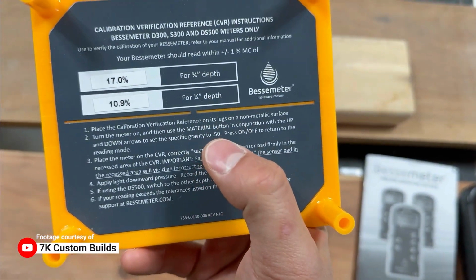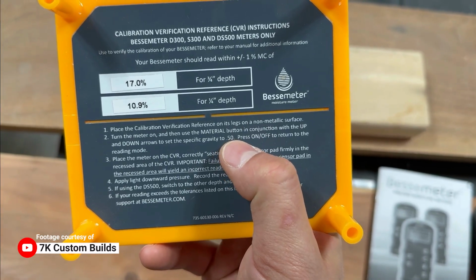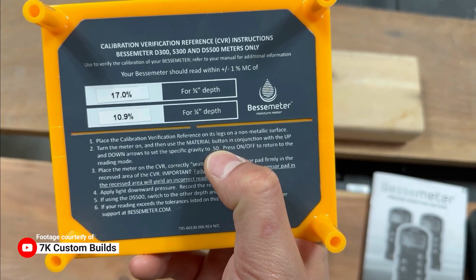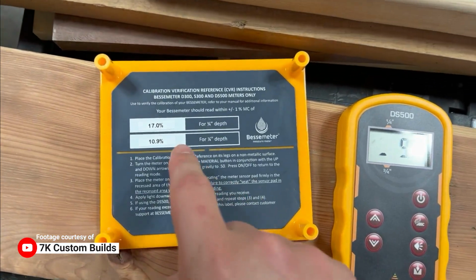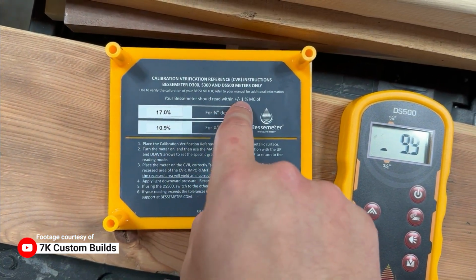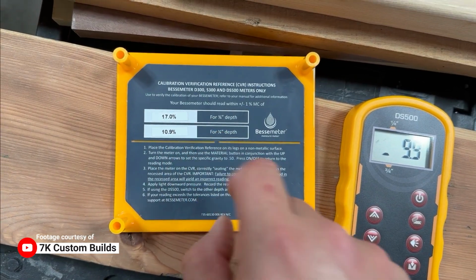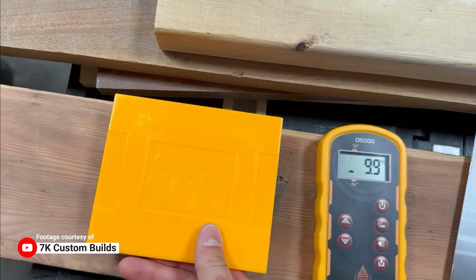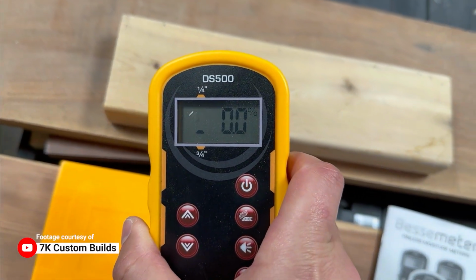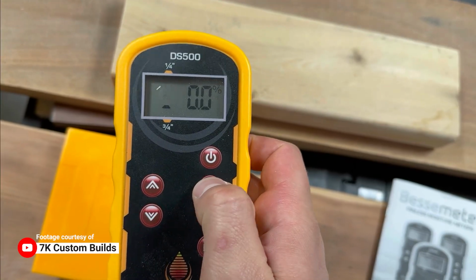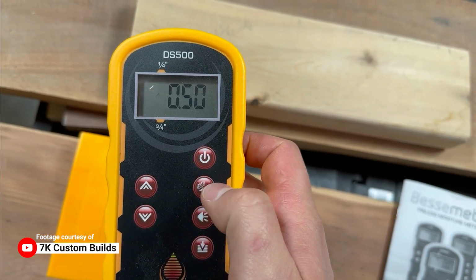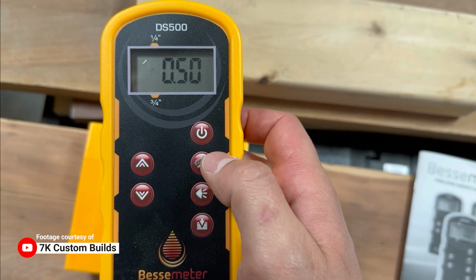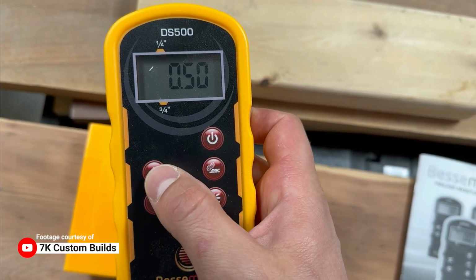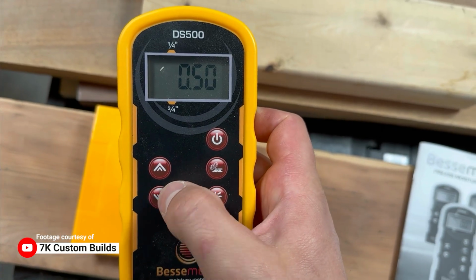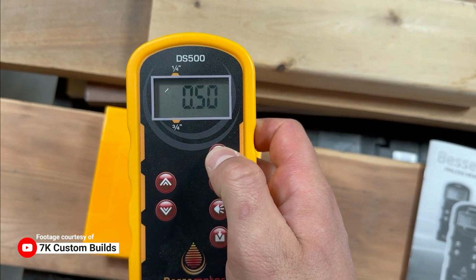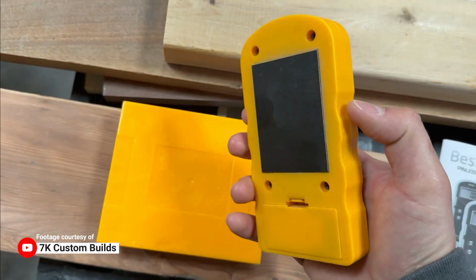So you can read through all of this, but basically we need to set the species setting to 0.50, and then we need the numbers to be within those parameters, within 1% of those parameters for the two different settings. So since I'm currently on the 3/4 inch setting, I need to make sure my species is 0.50. It is. So this second button is the species button. You can change that up and down with the toggle arrows, and then to select it you press the power button again, and we're in the 3/4 inch setting.